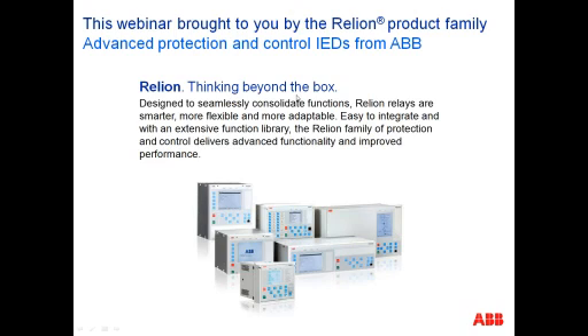A circuit breaker is a physical device. So I model my relay with logical devices or logical nodes, and if I have an overcurrent unit that I want to operate, this logical node is referred to as a PTOC in 61850 logical node terminology, and that PTOC has certain characteristics that define it. I would map data from that PTOC to a circuit breaker, whose model is defined as an XCBR, and it has certain characteristics. So it allows me to do, I guess the best way to say it is, point-to-point wiring, but in a logical sense. I'm taking data from one and sending it to the other. The other reads that data and will act upon it appropriately.